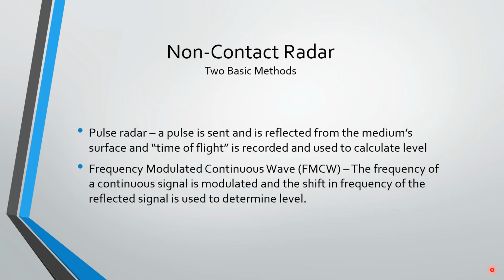Okay, so that covered guided wave radar, which is time domain reflectometry, and it is a contact-based radar level measurement system because there is a probe or a cable that has to come in contact with the medium being measured. Now we're going to switch over to what we call non-contact radar. Some people call this free air radar, okay? And there's basically two different methods of doing non-contact radar.